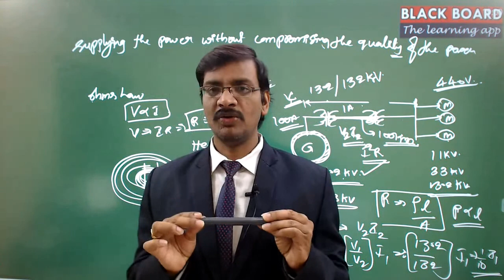So two important factors we have achieved. One is that material is saved to a greater extent. This is fundamental, because the area of cross section is reduced by reducing the current. So you can use a very small amount of material, because a very small size of conductor is sufficient to transfer power of a higher magnitude. So MVA power can be transferred very easily with a smaller amount of current.